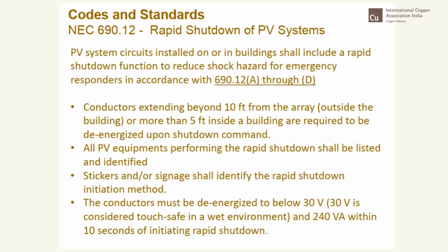If only these kinds of rapid shutdown systems had been installed in PV system circuits, several hundred thousands of dollars of destroyed property could easily have been avoided. But then you realize that this NEC code came with greater emphasis in 2014, because that was a great learning. So the conductors extending beyond 10 feet from the array outside the building, or more than 5 feet inside the building, are required to be de-energized upon shutdown.